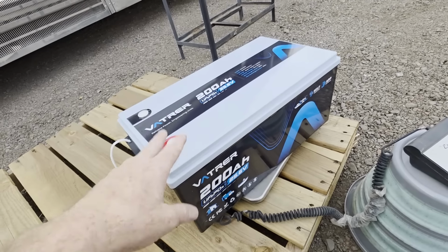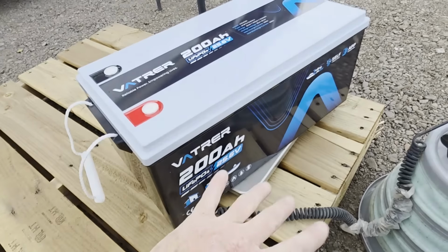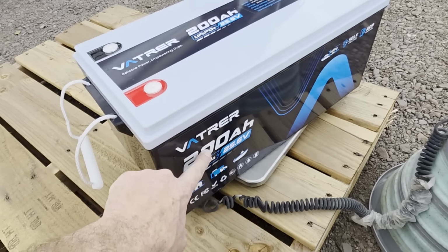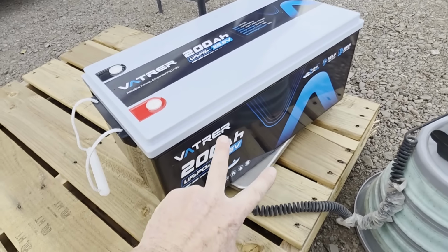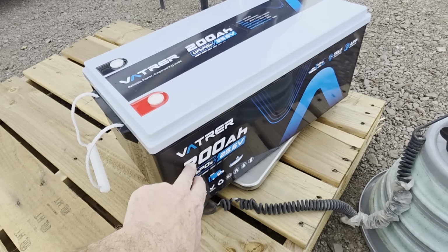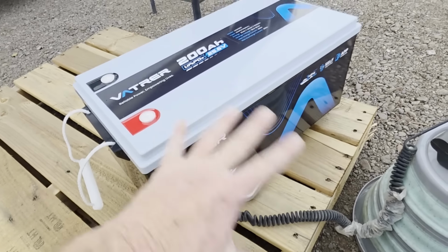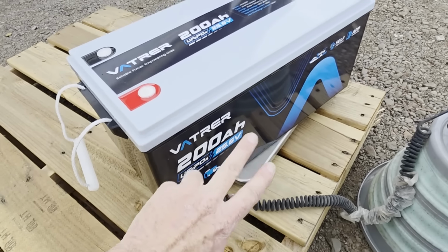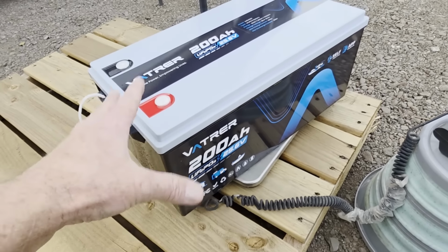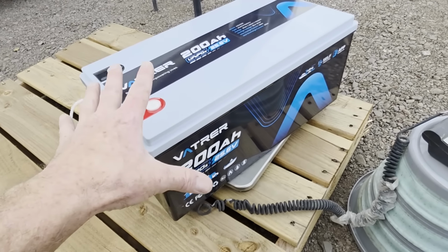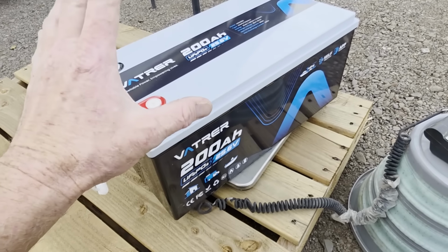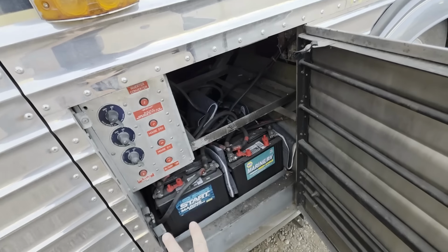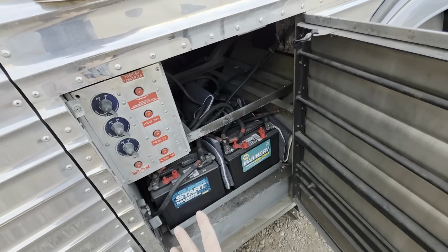If we wire up two 12 volt batteries in series, we double the voltage, but the amp rating stays the same. So two 12 volt 200 amp hour Vatrer batteries wired in series would still only give us one 200 amp hour 24 volt battery. I felt using individual 24 volt batteries was the best way to maximize power density in this small compartment.